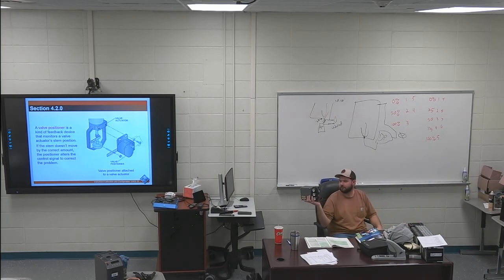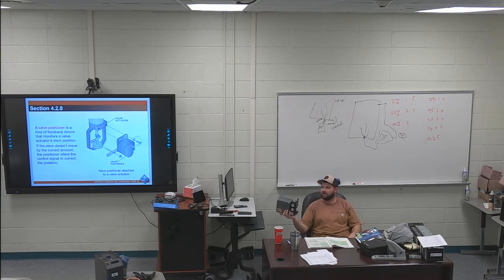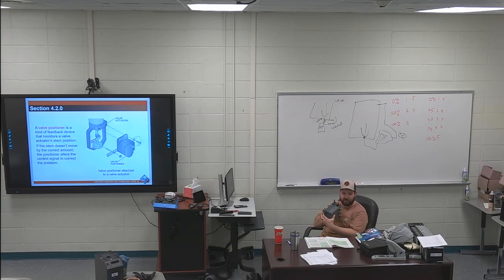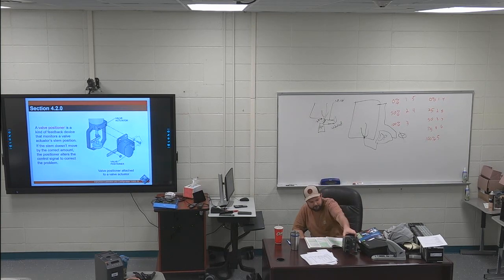Analog positioning. So this would screw, like the big tall valve over there, this would screw to the front of that valve, and then the valve stem in the middle of that would attach to this, right? And as that valve goes up and down, this creates a signal on the inside, like this valve is 50% open, this valve is all the way open, or this valve is all the way closed. So this is a valve positioner, and if whatever is in the control room input signal doesn't match where it's saying the valve is, this will physically send either more or less air to the top of that valve to either open or close it.